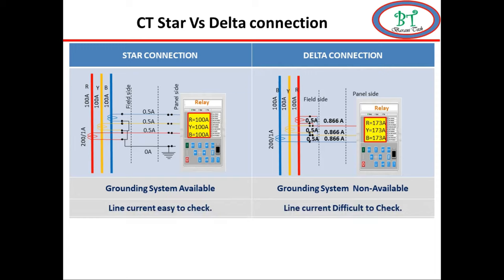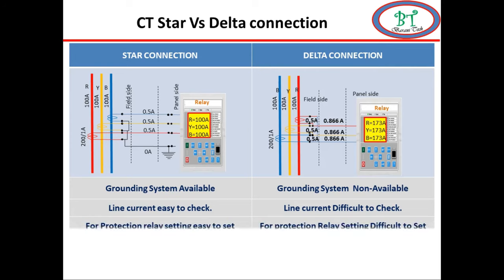Next, for relay settings, for all current depending protection like over current and all other protection, it's very easy to set for star connection CT because all protection is directly set with line current.